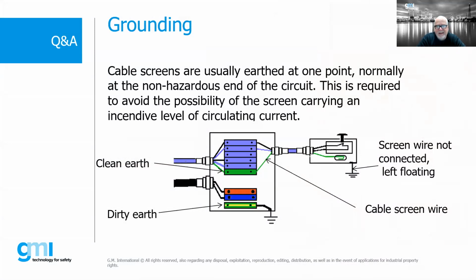So this is how we would deal with screens typically on IS circuits or instrumentation cable. We're going to land them into additional terminals, but we're going to bring those all the way back into the safe area. Sometimes we'll leave them floating in the hazardous area. When we leave them floating, one of the requirements is we don't want to use things like tape. What we would say with that screen wire, we would take sleeving, heat shrink, cold shrink tubing, put a cable tie on it or an insulated cap, and that's how we deal with our screens or drains with regards to hazardous locations. Best bet, if we have extra terminals, is go ahead and treat them as a spare core and install them into an unused terminal block.